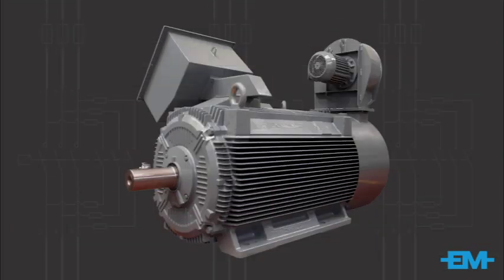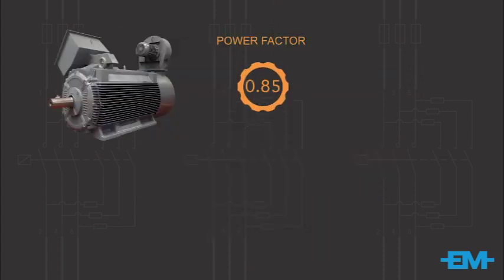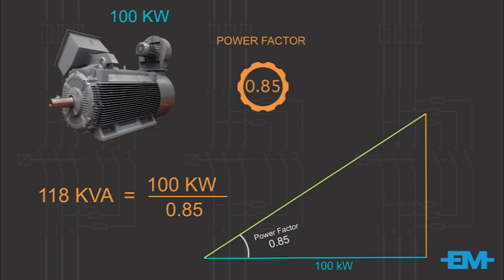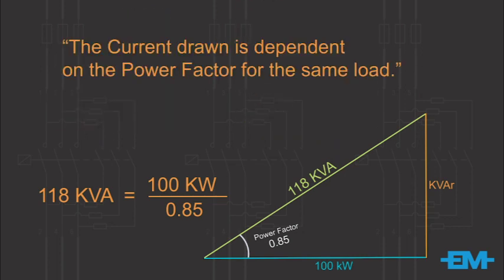A large electric motor might typically have a power factor of about 0.85 at full load. Let's say our motor is rated at 100 kilowatts and the power factor is 0.85. The electricity supply would have to supply 100 kilowatts divided by 0.85, which equals 118 kilovolt-amps KVA, to provide the 100 kilowatts to run the motor. That means they would be supplying 18% more electricity than they are charging for, which is why power supply measures maximum demand KVA — because the current drawn is dependent on the power factor for the same load, and the current drawn is calculated with KVA.